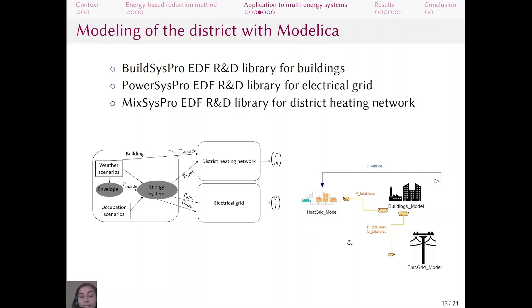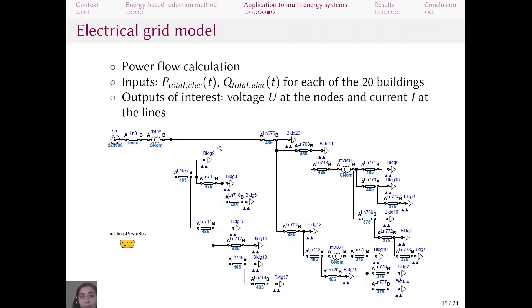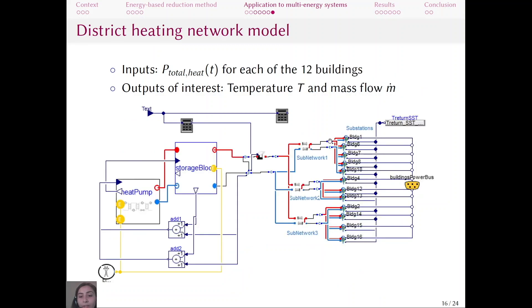Here we can see the model in Dymola. The buildings model is composed of 20 buildings, each with one envelope and one energy system. Weather and occupation scenarios are the inputs. The outputs feed the electrical grid model and the district heating network model. In the electrical grid model, we have power flow calculations; the active and reactive power demands are inputs, and we are interested in voltages at nodes and currents at lines. In the district heating network model, 12 buildings are divided into three sub-networks, each taking heating demand as input, and we are interested in temperature and mass flow at the substation level of each building.